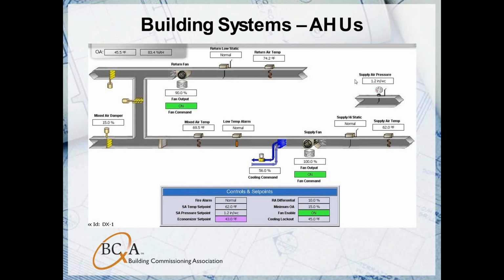Up on the screen, we have an example of the Niagara BAS graphics. This is one of the 4 main building air handlers. The air handlers are located in the penthouse, which is the 25th floor of the building. There are 4 identical 125,000 CFM air handlers, each with a 250 horsepower supply fan and a 100 horsepower return fan. Each supply fan is controlled to its own down duct static pressure sensor. So each unit is controlled to a separate static pressure sensor.